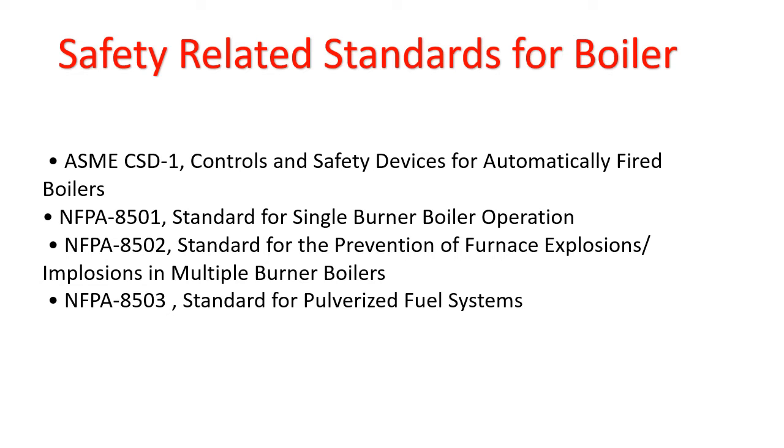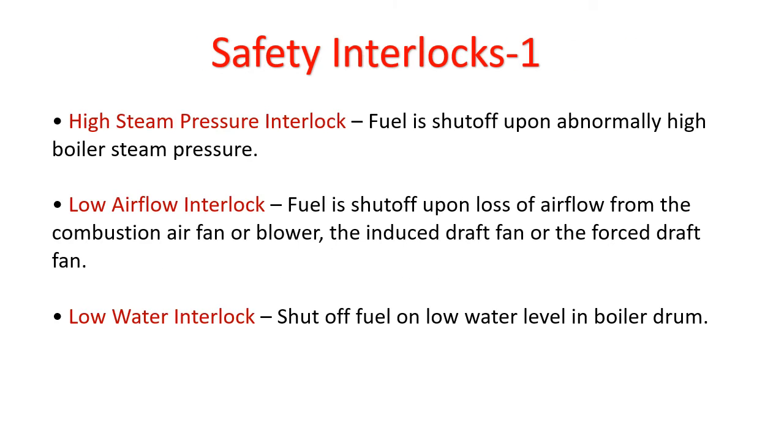Then there are NFPA 8501, 8502 and 8503. Now, 8501 is for single burner boiler operation. 8502 is for the prevention of furnace explosions and implosions in multiple burner boilers. And 8503 is the standard for pulverized fuel systems. So these are commonly used safety-related standards for boilers.